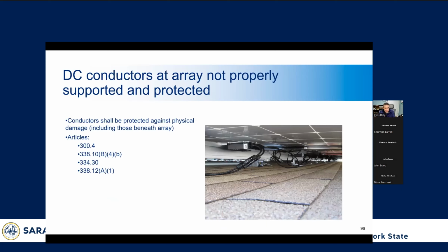One of the most common installation errors that we see on a rooftop particularly is where the conductors are not properly supported, and they're just laying on the roof where they're subject to damage by wind, snow, ice. The wind can move those around, cause them to run along the abrasive shingles and wear away that way. So that's a potential problem. The wires can also catch debris moving down the roofs, which can cause drainage issues and then cause problems with the roof.